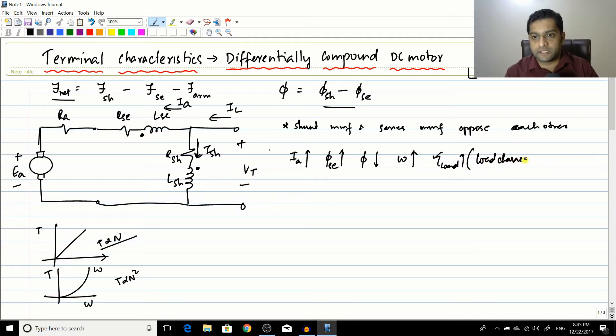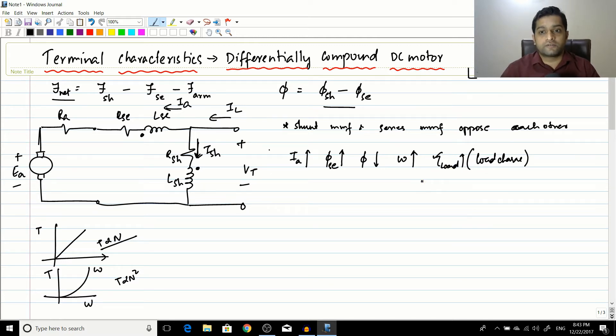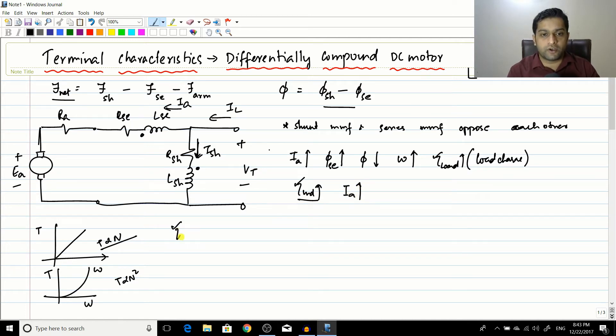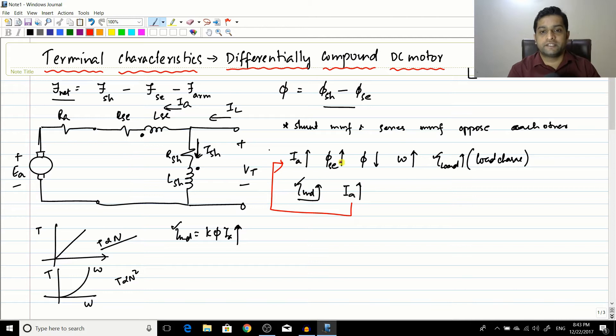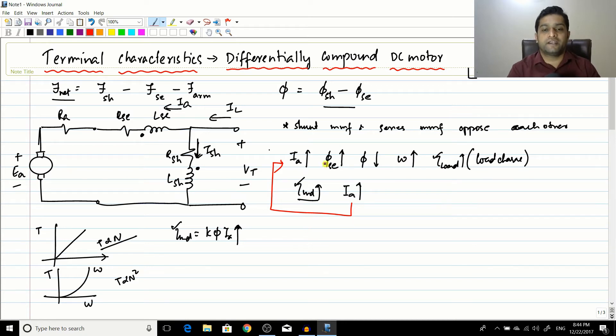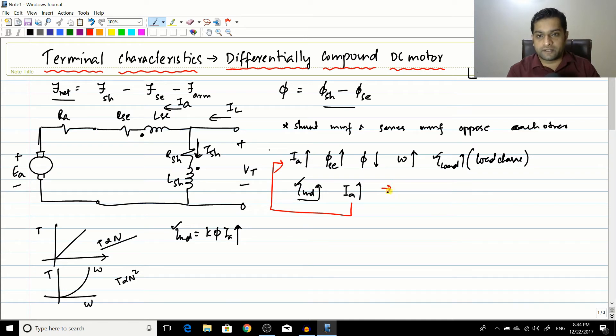To compensate, the motor has to induce more torque, so torque induced increases. That means Ia must increase. As Ia increases, series flux increases, net flux decreases, omega increases again — and load torque increases again. This cycle keeps repeating: Ia increases → series flux increases → net flux decreases → omega increases → load torque increases. This is called a runaway condition.